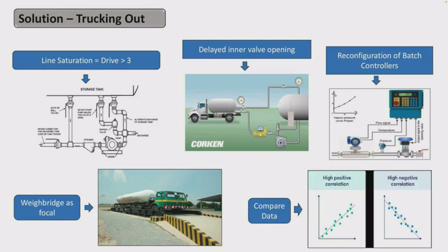This liquid return line is always saturated with product. So what we normally do when we see that movement is open it up, line up the liquid return line to supply some of this product into our discharge line. In doing so, that product helps saturate the discharge line, and then your flow meters are perfectly aligned, and we stop having that movement. So once in a while you see the movement, but it's now part of our SOP - you just open the return line, it saturates, and you stop having the reading. Maybe 1, 3, or 5 kg moved - not a problem for the company.